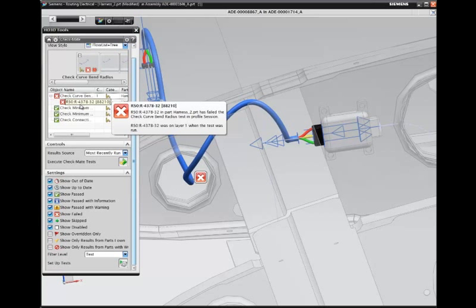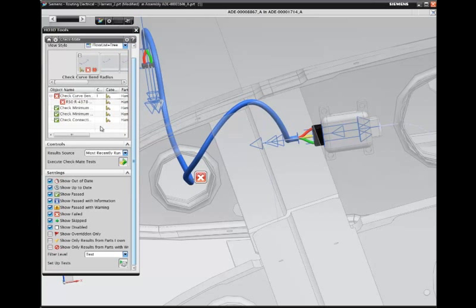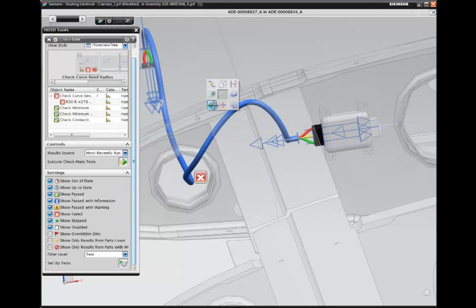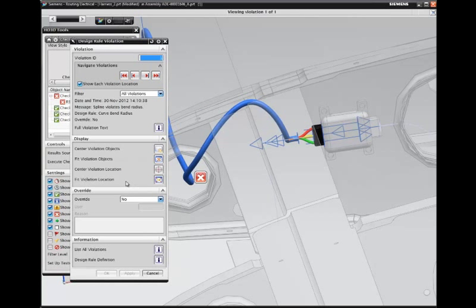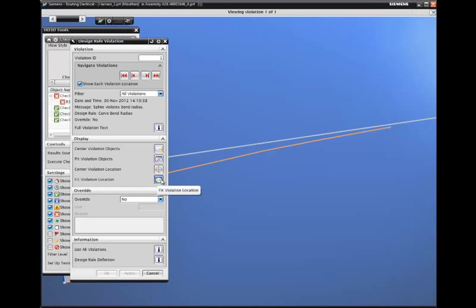When the checks are done, a visual tag indicates a component that did not pass the check. We can look at the details and determine that the cable did not meet one of the bend requirements. We can zoom in to visually inspect and correct the problem.